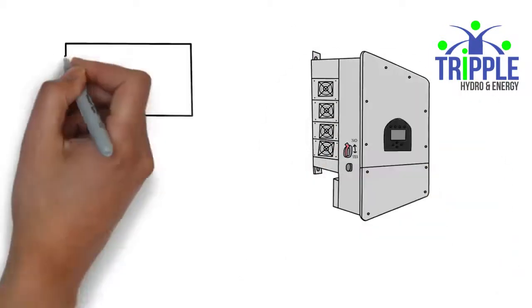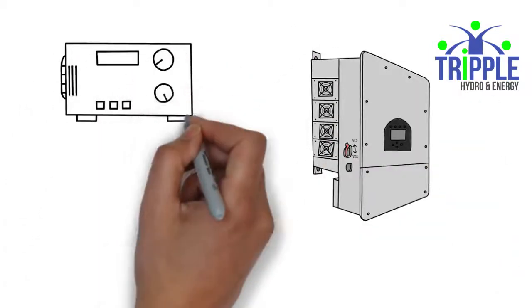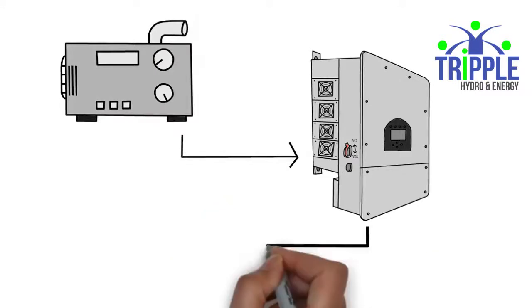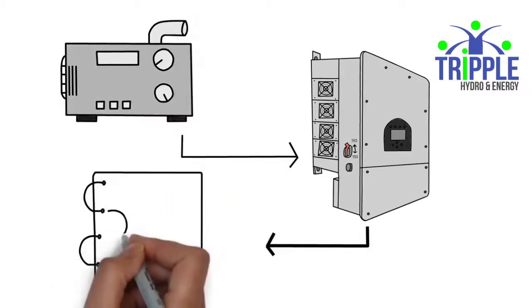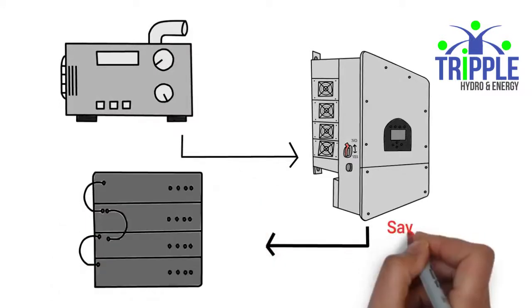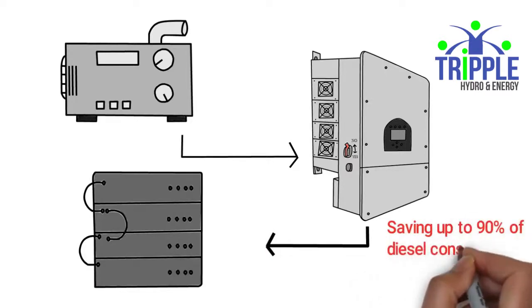The inverter can control a generator in a similar way to a hybrid car, in that the generator will only be used when the batteries are depleted to a certain level, thus saving up to 90% of diesel consumption, thereby reducing the frequency of fuel deliveries to remote locations.